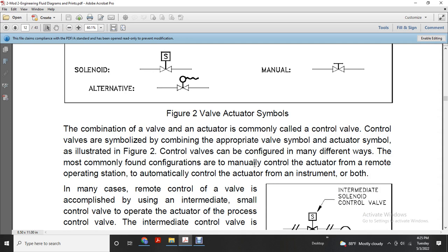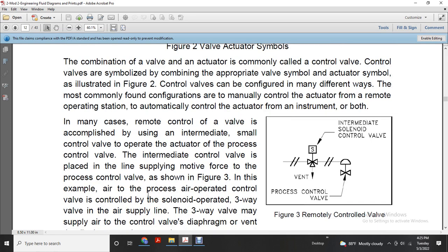The control valve symbol is combined with the appropriate valve symbol. The actuator symbol is illustrated in figure 2, but control valves can be configured many different ways. The most commonly found configurations are manually controlled, with the actuator operated from a remote station, and automatic control, with the actuator controlled by an instrument, or both. In many cases, remote control of the valve is accomplished by using an intermediate small control valve that operates the actuator, supplying motive force to the process control valve, as shown in figure 3.